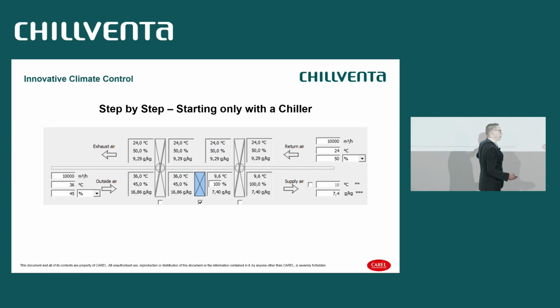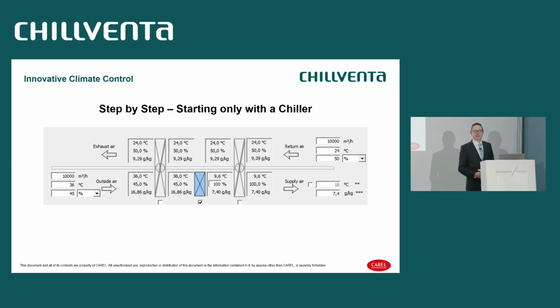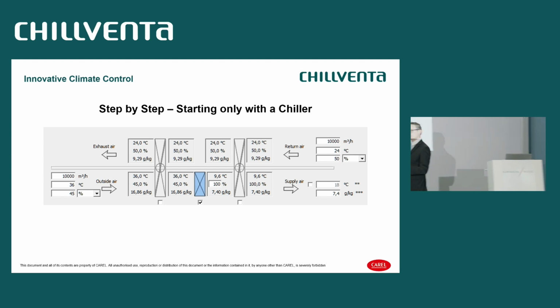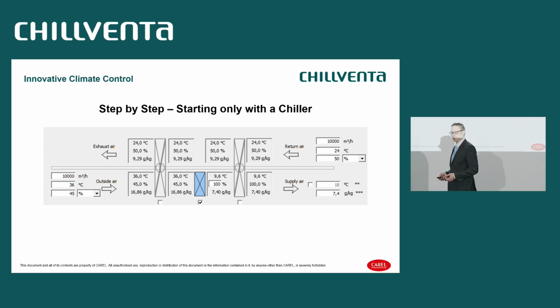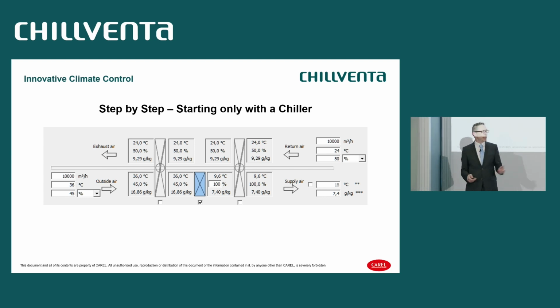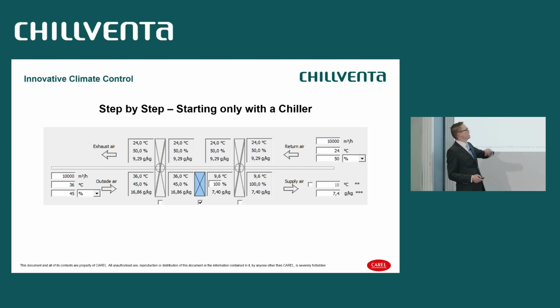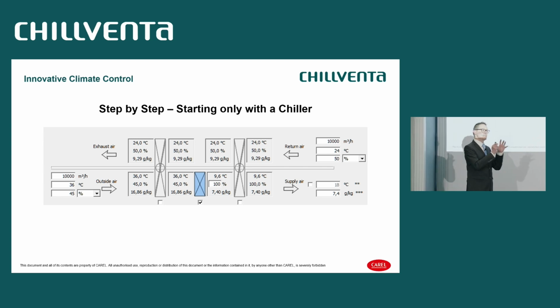You can see here the blue square is the symbol for the chilling or the chiller system. The idea is to go from 36 degrees, 45% RH, which is quite hot, quite humid, not very comfortable, makes you sweat even in the shadow, and we want to have something like 18 degrees and 7.4 grams inside the room. In such hot areas, you need to cool down the air that enters the room below your target.